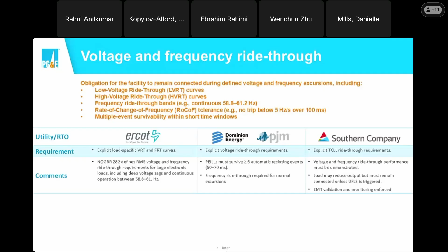Along with those ride-through curves, they've also got the requirement, which is what you see for example in AEP and Dominion, where you are basically required to ride through 2 consecutive voltage excursions. And they also specify voltage bands within which you need to be riding through the event.